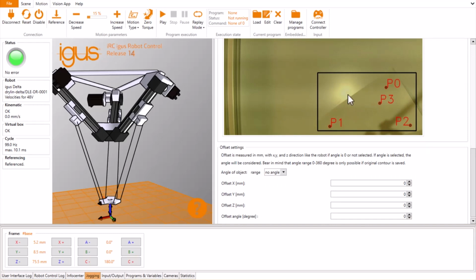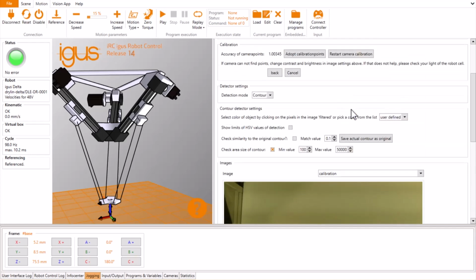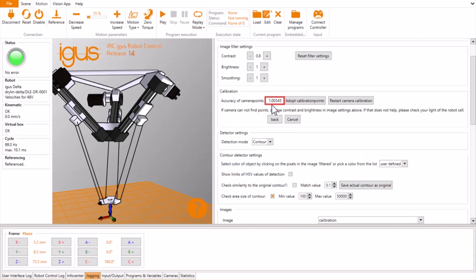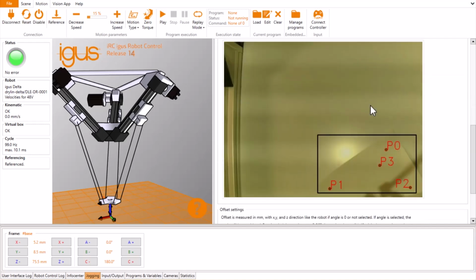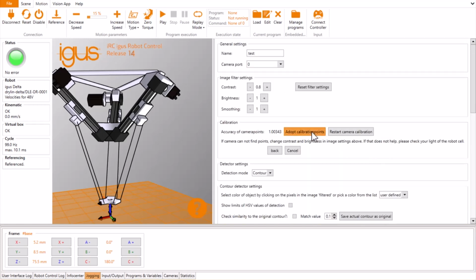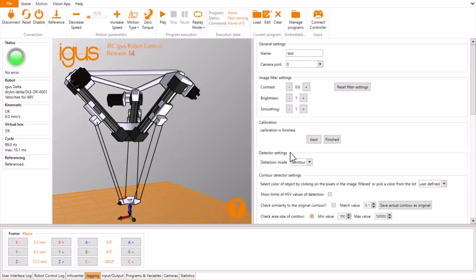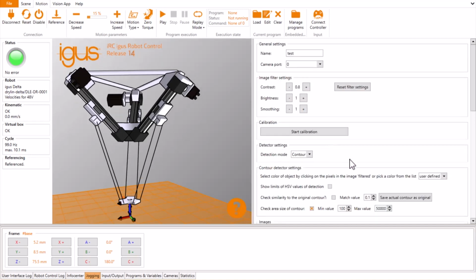An accuracy is also specified for the dots measured by the camera, which should be close to 1. If the 4 dots identified are wrong or the numbering is incorrect, start the calibration again. To ensure that no incorrect dots are saved, I make sure the numbering of the camera matches the numbers on the calibration sheet. If the 4 points have been identified correctly, you can save the dots and end the calibration. You can reset the image filter settings and remove the calibration sheet. The camera is now fully calibrated and you can start setting the parameters so that your workpiece is identified.